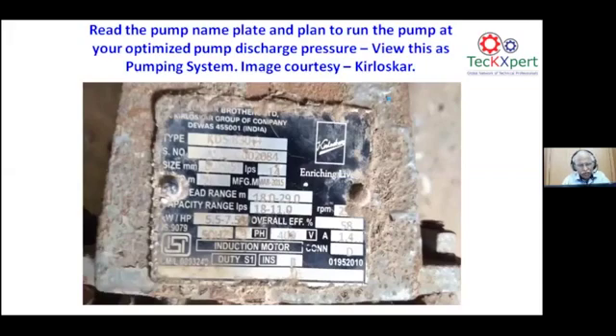Are we maintaining it? Let us say I am having a head range of 18 to 29 meters, almost 1.8 kg to 2.9 kgs. I am supposed to have 11 LPS at 1.8 kg, and we wanted to see whether we are optimizing the pressure for the given pump and the system. What does the process need and what is the system pressure the pump is giving? This needs to be monitored as such.